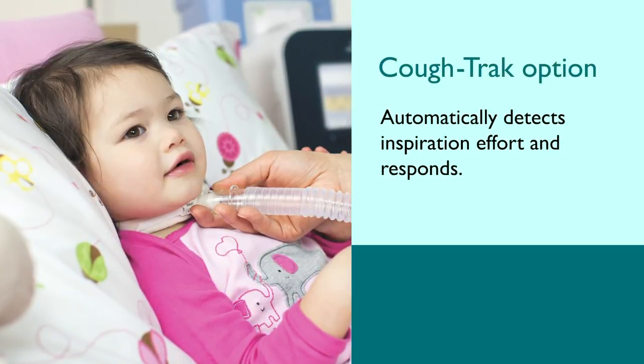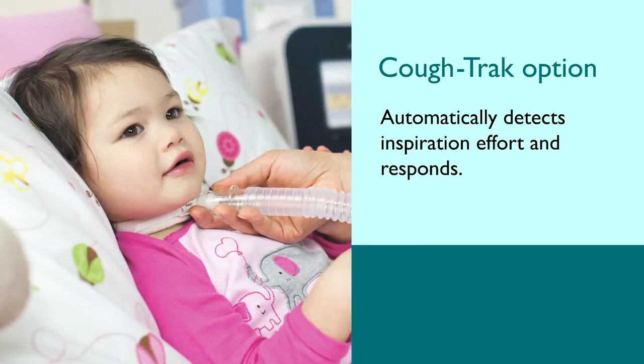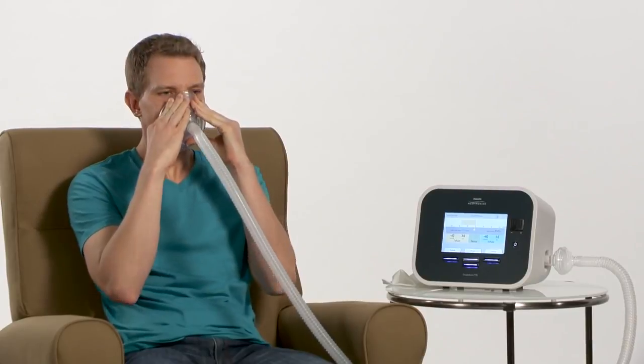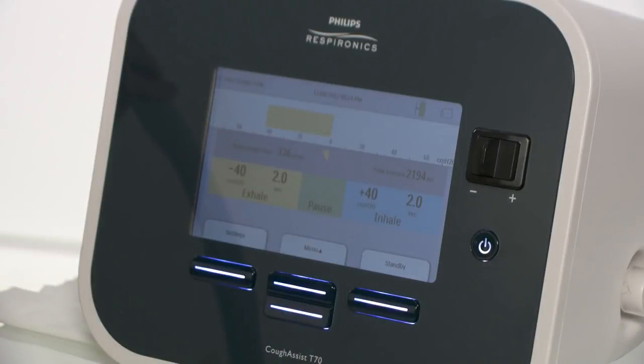When using the Cough-Trak option, the device will automatically detect inspiration effort and respond with an inhalation. With automatic operation, there is no need to toggle the manual switch between inspiration, exhalation and pause. CoughAssist T70 will do it for you and display the pressures in real time.